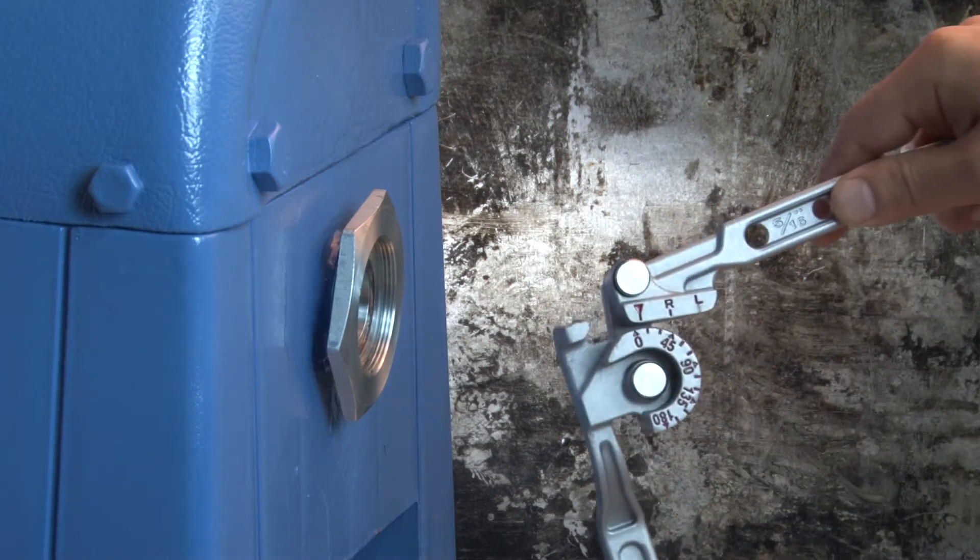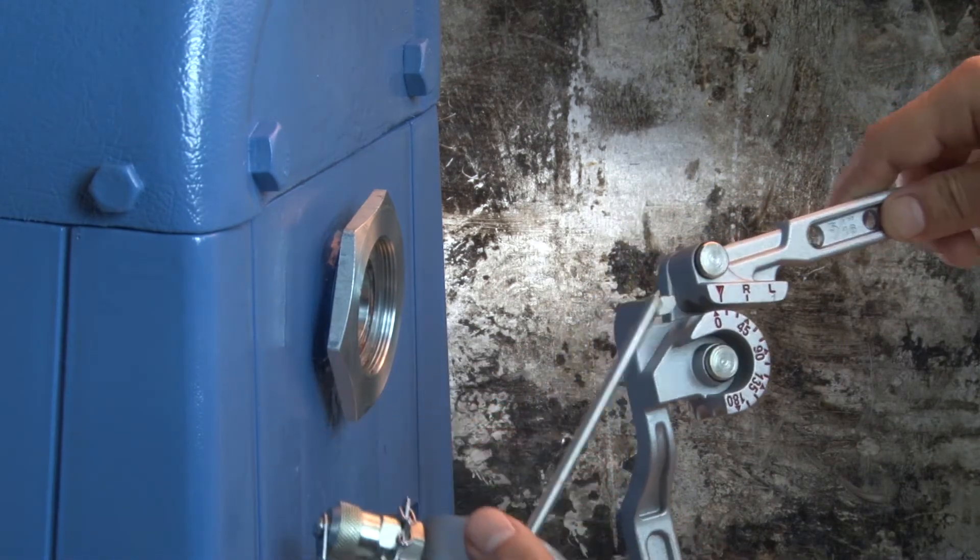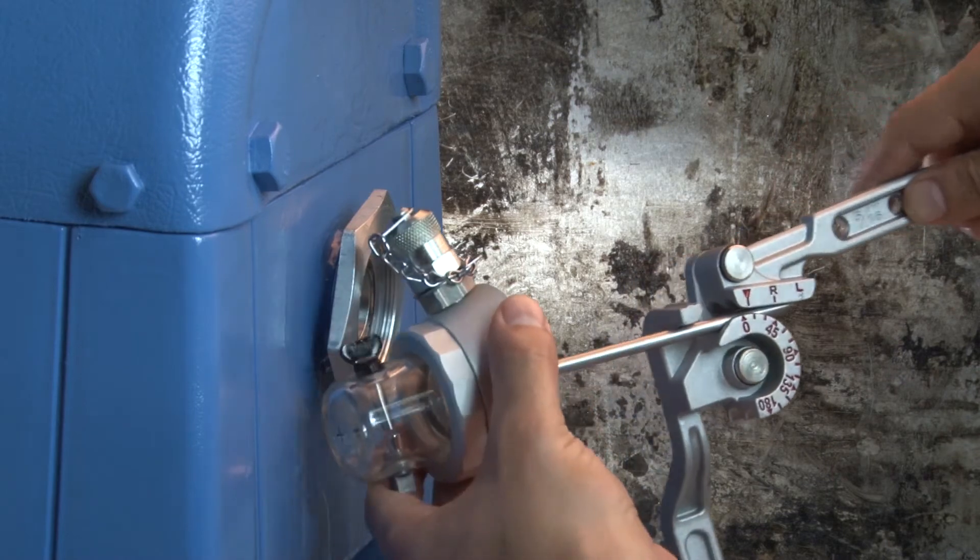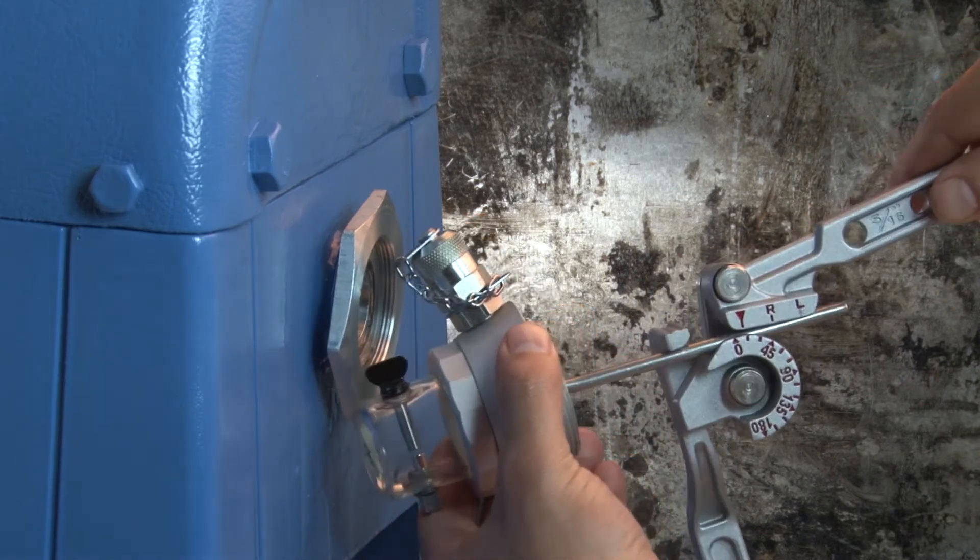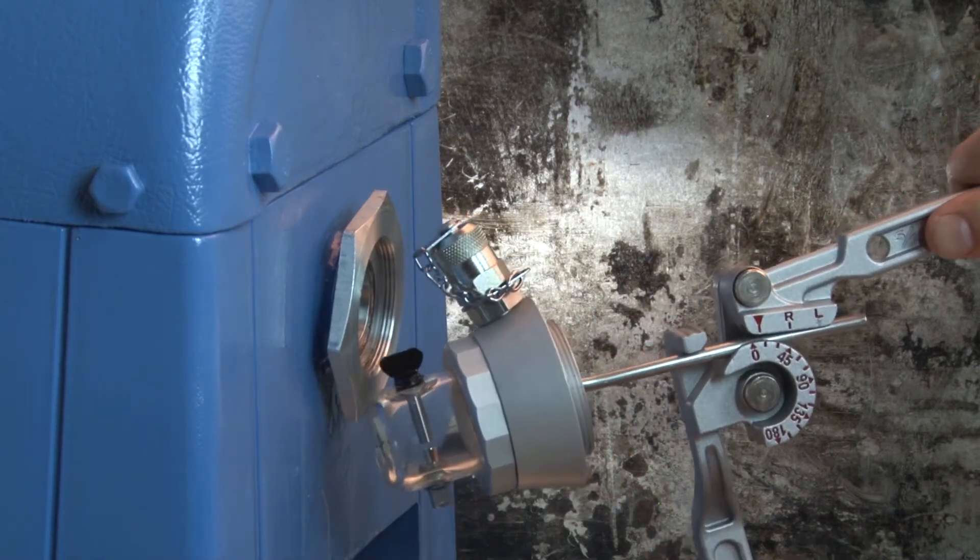Using the appropriate pipe bender, bend the pilot tube in the direction noted in the previous step. Choose a bend location and angle that place the pilot tube's tip within the machine and below the oil level for proper sampling.